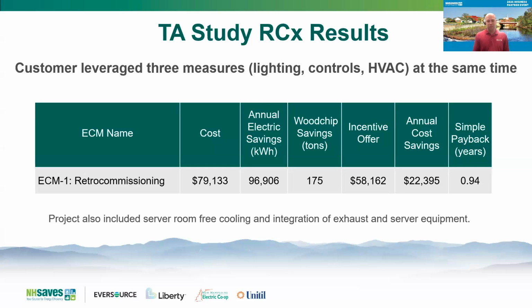This project also included a server room free cooling. They basically were able to switch their server room over to the free chilled water that they had instead of the mini splits and air handlers that they had in there previously. So that was a nice touch, as well as integrating some exhaust and server equipment that really didn't contribute a ton to the energy, but was something that the facility staff wanted to accomplish. So it was an example of just being able to leverage energy and operations under the same project and have the overall total project still have a great payback.